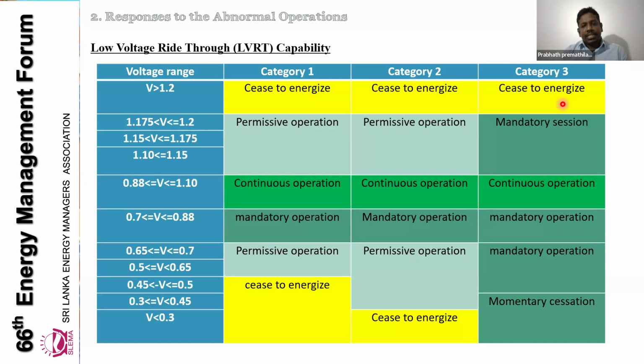In the mandatory operation mode, it needs to maintain synchronism. It needs to inject power. And in some situations, if the system is forced to disconnect, how the power comes back again is what we call entering the service.